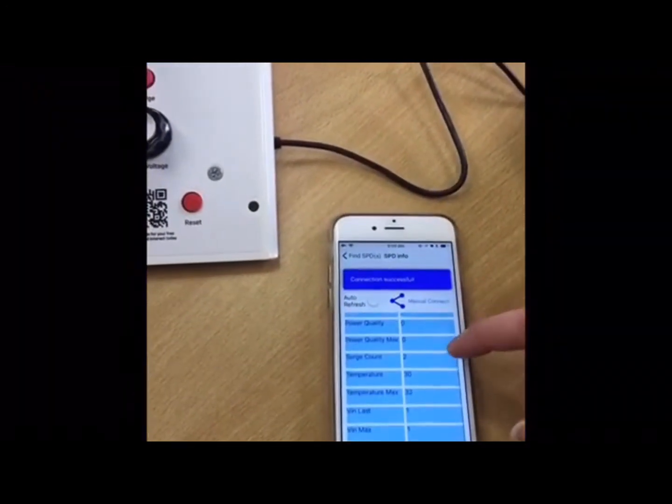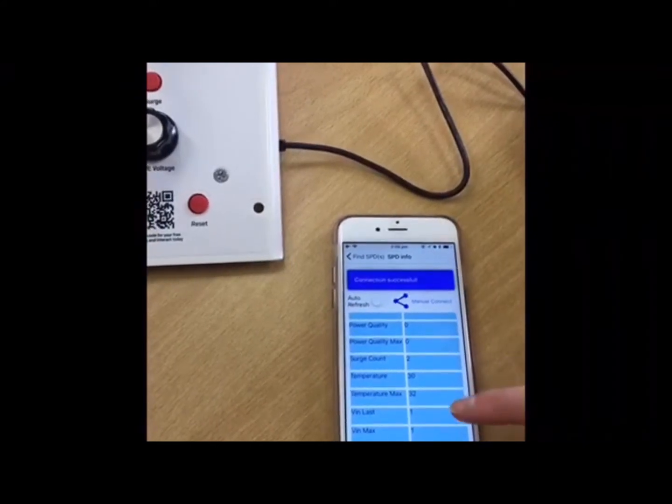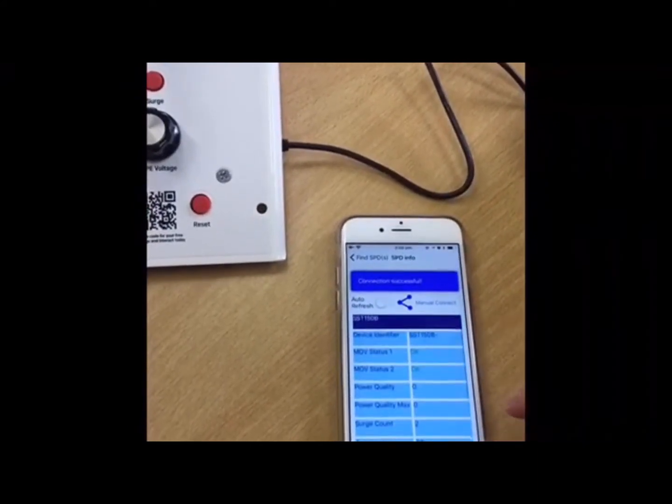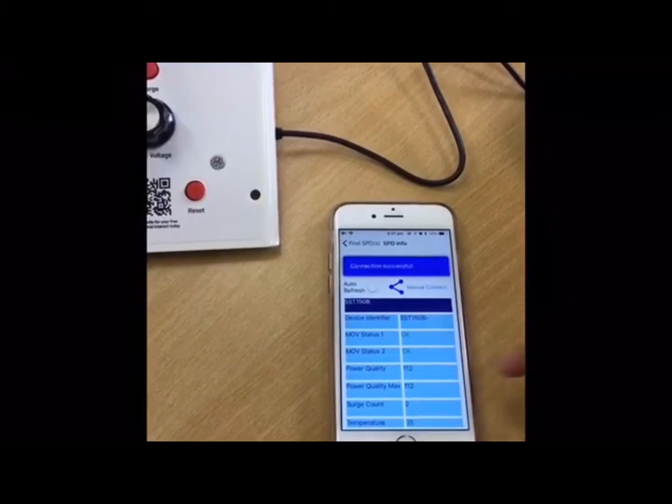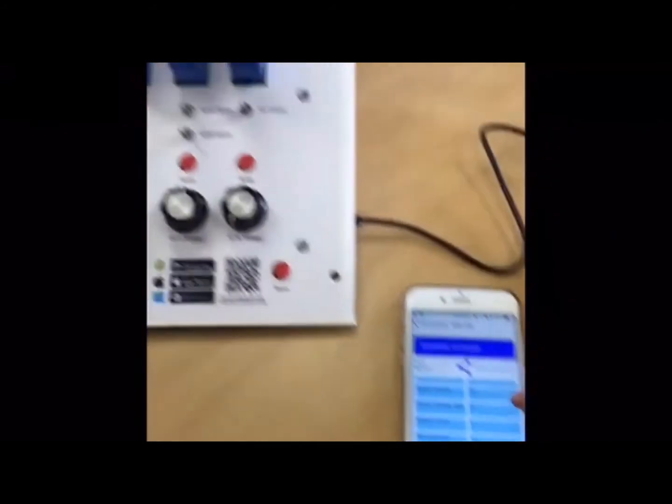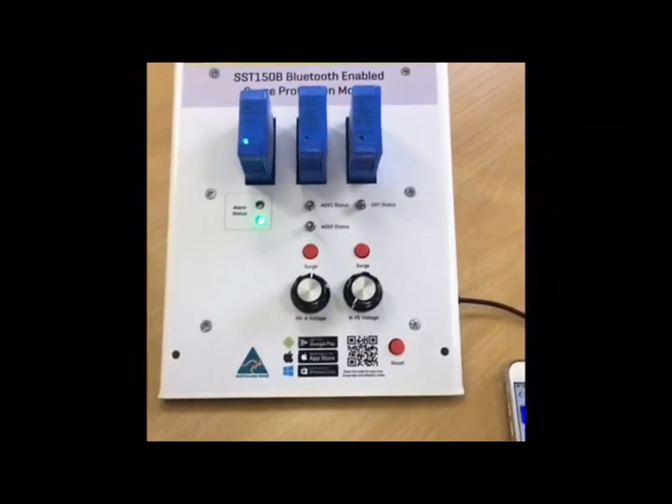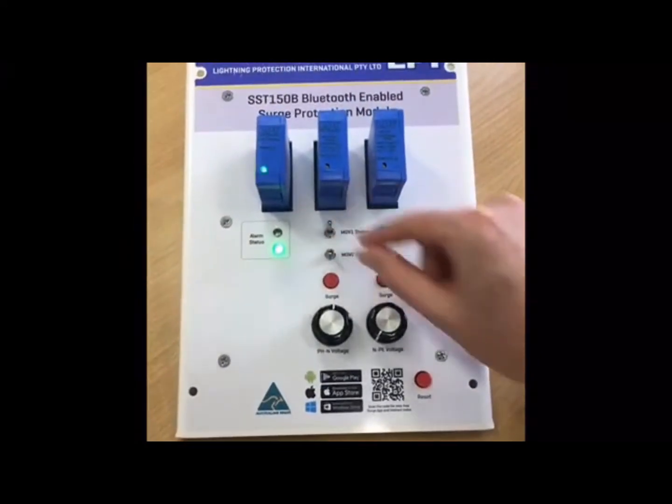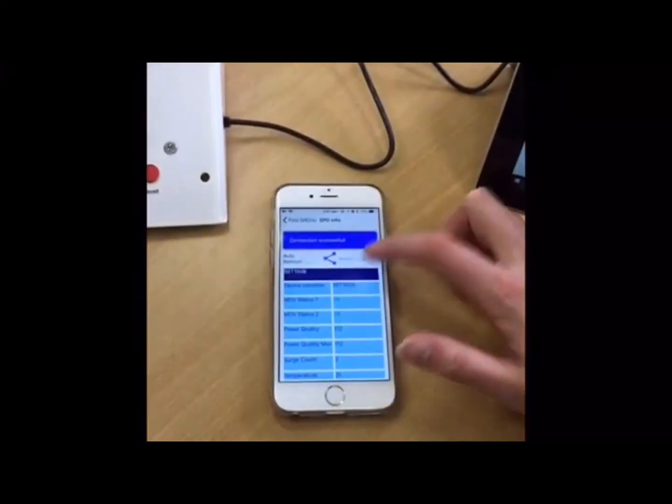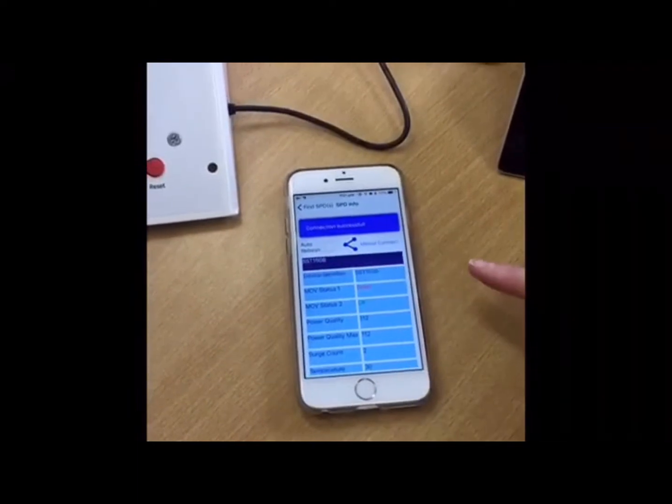The SST150B modules use two metal oxide varistors or MOVs as part of its hybrid protection circuit. To simulate an internal fault, toggle either the MOV1 or MOV2 switch. You can now see the MOV status in the SPD app has changed to fail.